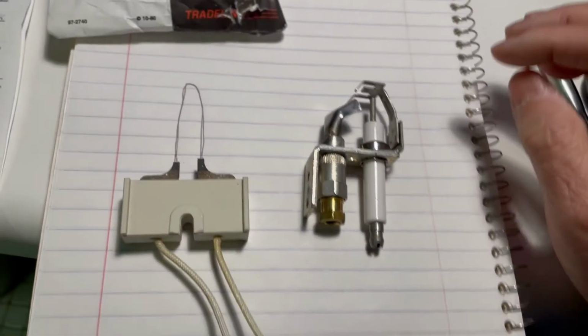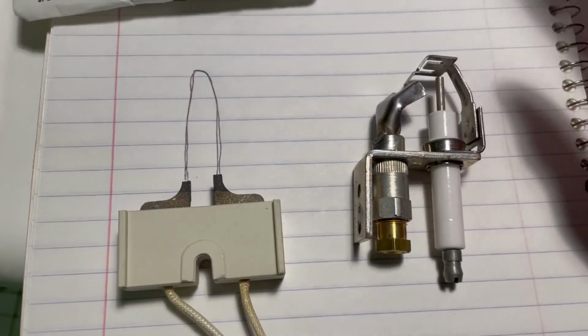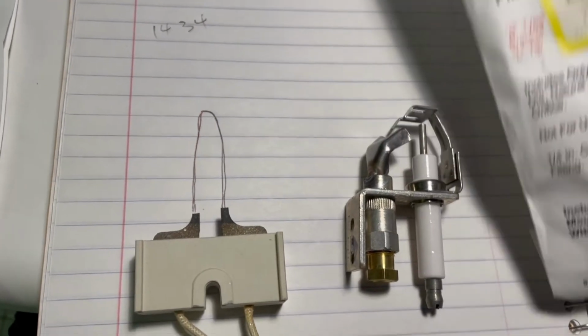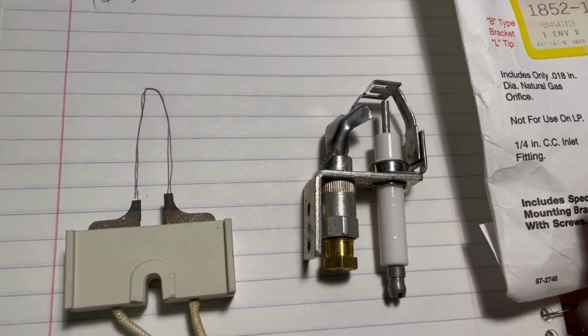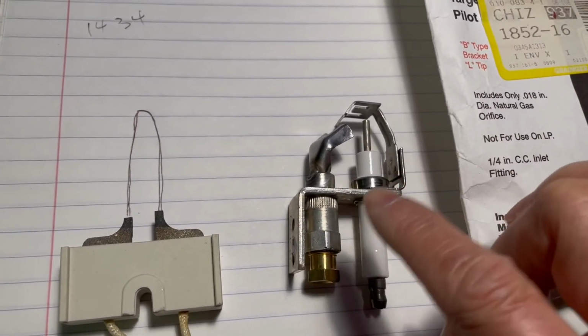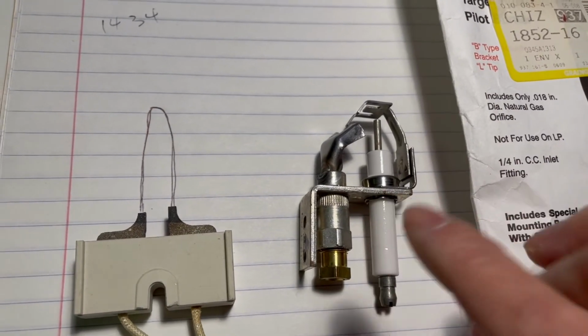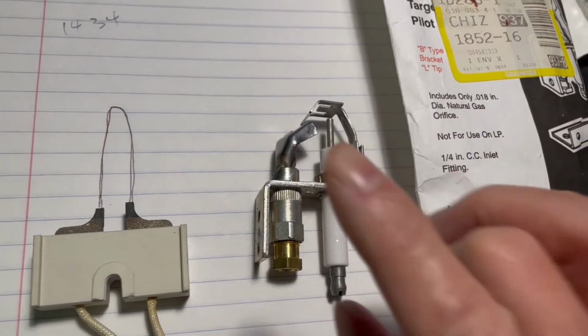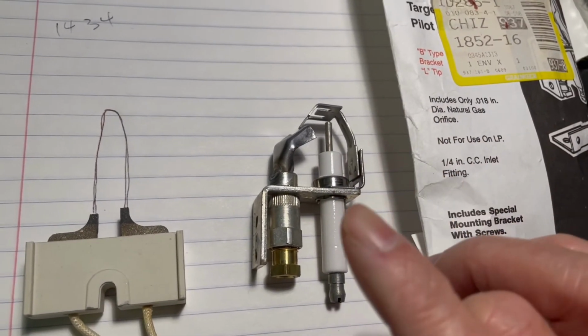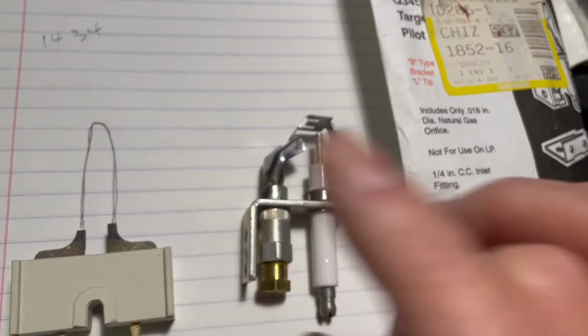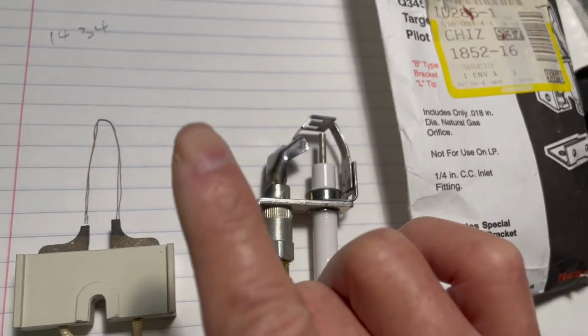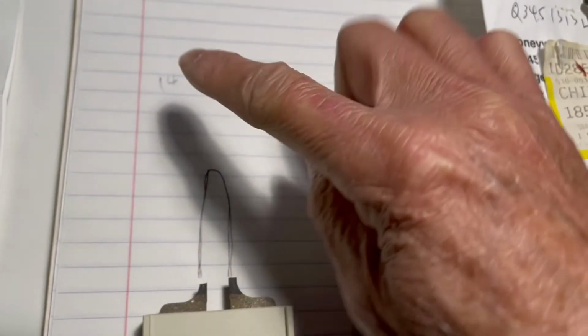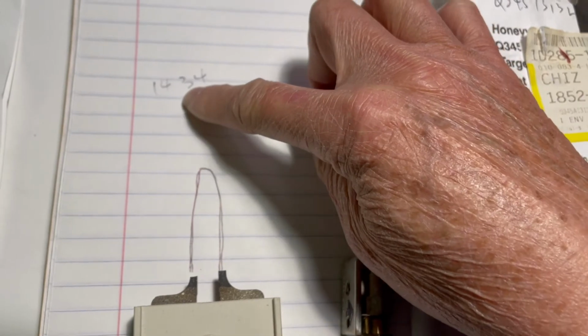And usually on your boiler or furnace, you would get an error code. For some of the Bryant ones, the gas furnace would show like 14 or 34. It would have a blinking LED light. The first blink, short blink, is for the first number, and the long blink is for the second number.